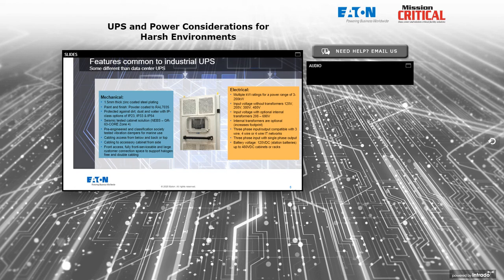The input and output can be single-phase or three-phase, so it is common to request a three-phase input and a single-phase output, typically a four-wire, three hot wires and a neutral and ground, or what's called an IT distribution network.